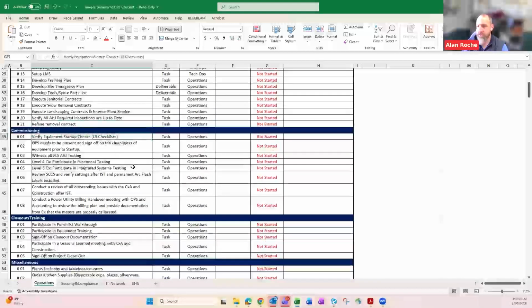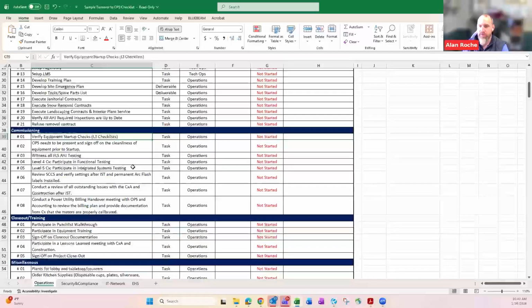Then some more specifics here in the commissioning - verifying level 3 checks, ops being present for all the pre-energization inspections prior to startup, witnessing all the AHJ testing, and participating in level 4, level 5. A big one is reviewing the coordination study and verifying settings after IST, after the permit, and verifying the permanent arc flash labels are installed - we want to make sure we have those permanent ones installed and no construction temporary ones, and that all the breaker settings, if we had to adjust anything during IST, are finalized so the coordination study matches what's being turned over to operations.